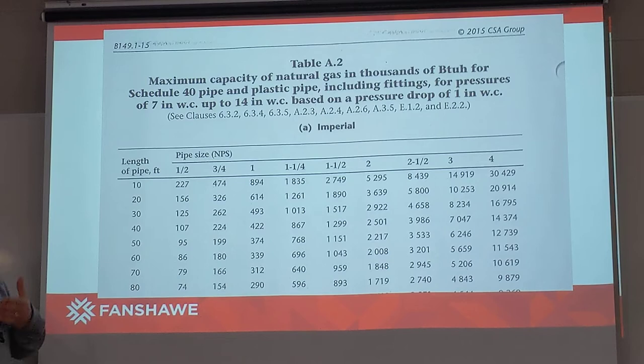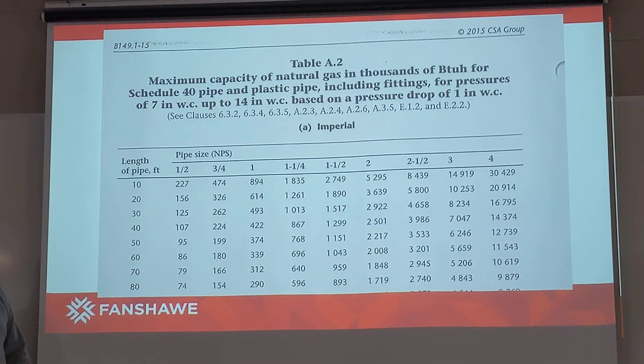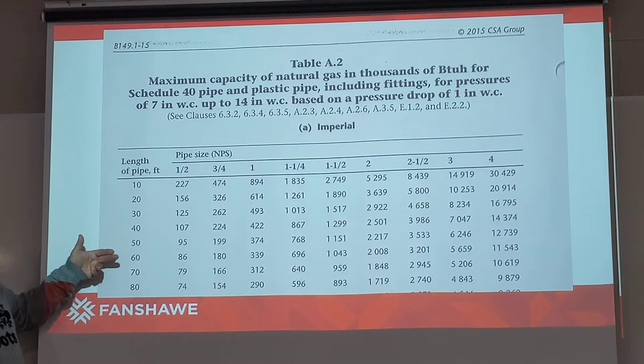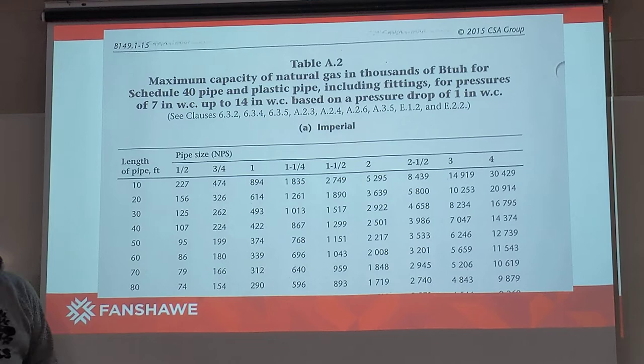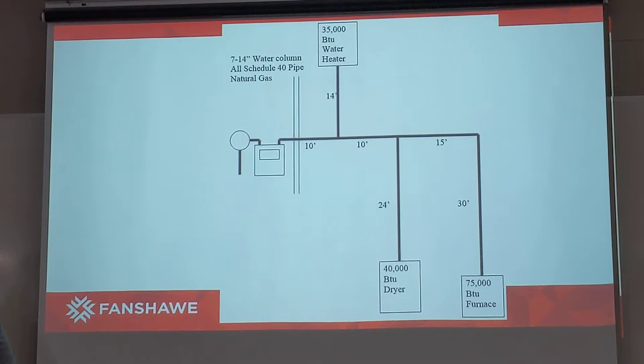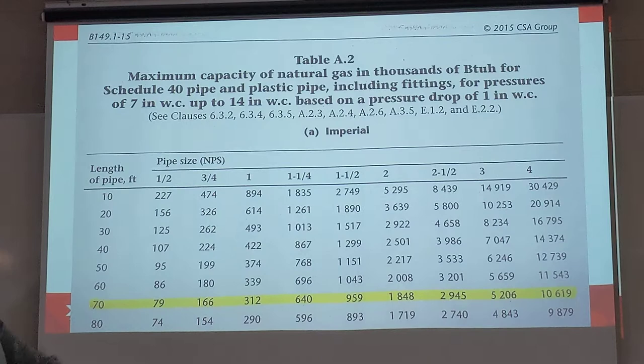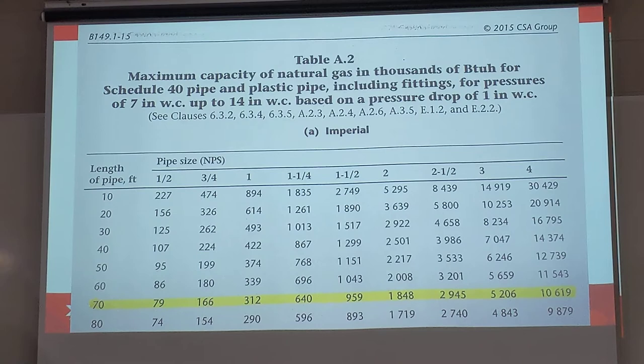Even if we were at 61 feet, we would still go to 70 feet. The only time we go back to the shorter run is when that number lands exactly on or is less than that value. So 61, 62, 63, 68, 69 feet — it doesn't matter, it all goes to the 70-foot code zone. Because we're using the 70-foot code zone, which already contains our longest measured run, I've highlighted the 70-foot code zone, and we'll start sizing at the furnace first.